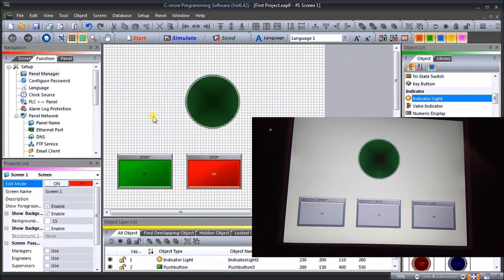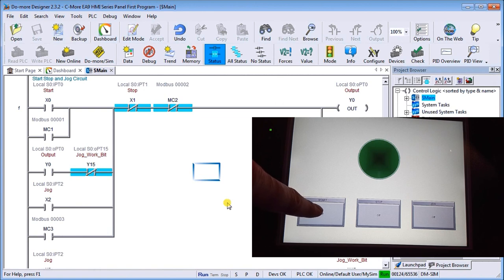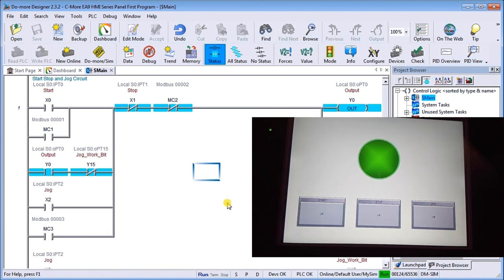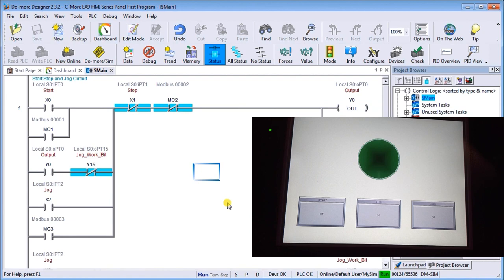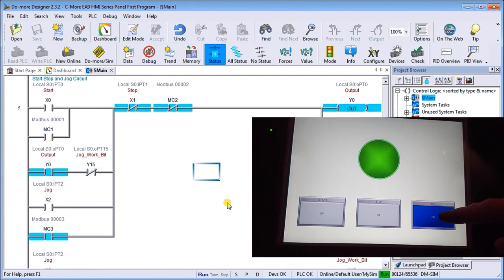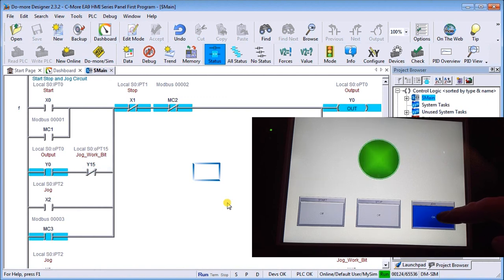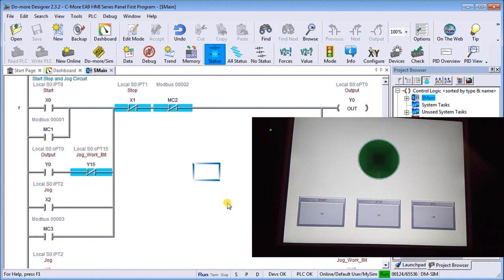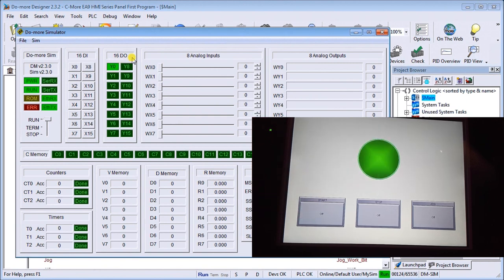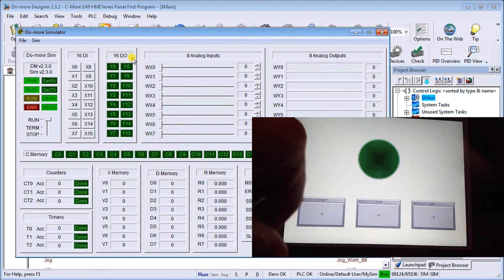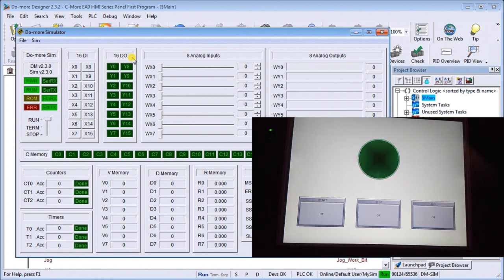Now we can look at our PLC software. You can see now if I look at my split display screen and hit my Start, my output turns on. Hit my Stop, it turns off. When I hold my jog, I can see that the light turns on and it goes off when I release it. That seems to be working fine. I can also see that in my simulator right now, there's my output. If I hit the on to start, turns on, stop turns off, and my jog. Everything looks like it's running just fine.